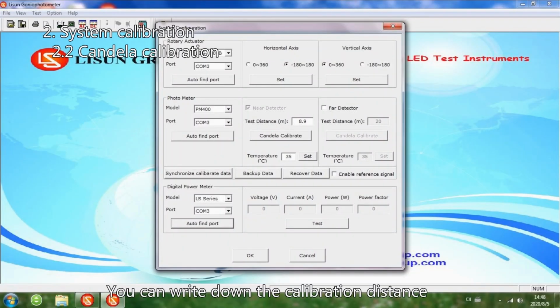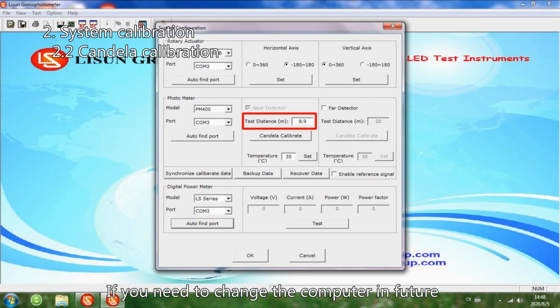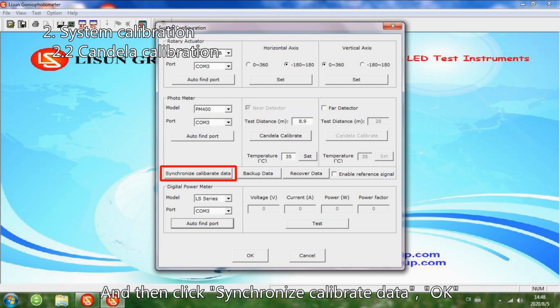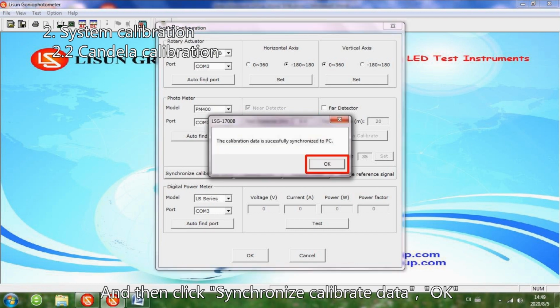You can write down the calibration distance. If you need to change the computer in future, you don't need to recalibrate the Candela. Just input the calibration distance manually, and then click Synchronize Calibrate Data, OK.